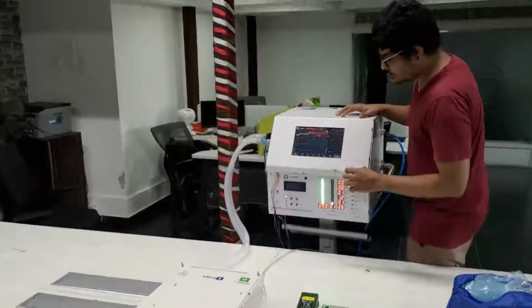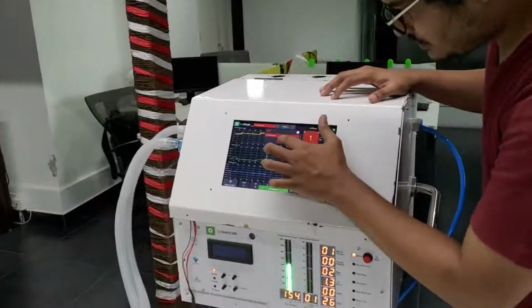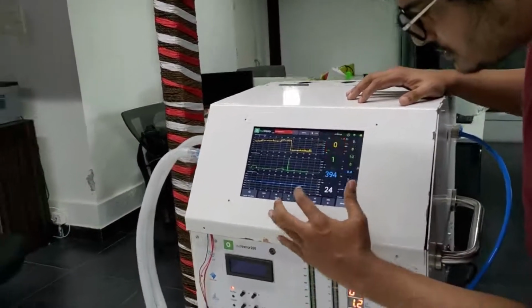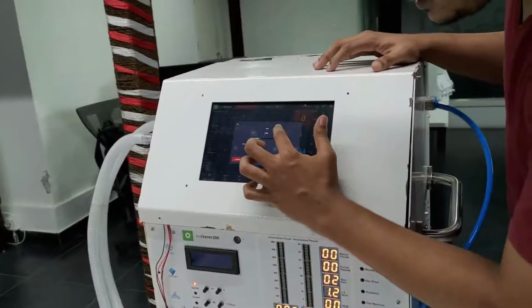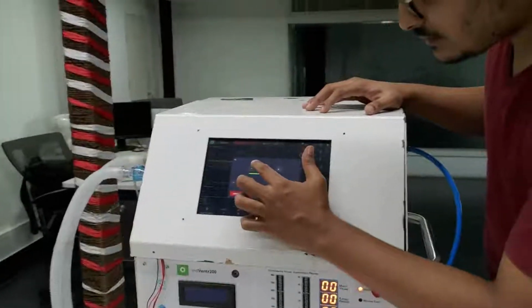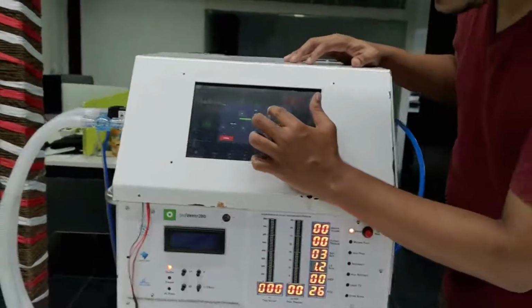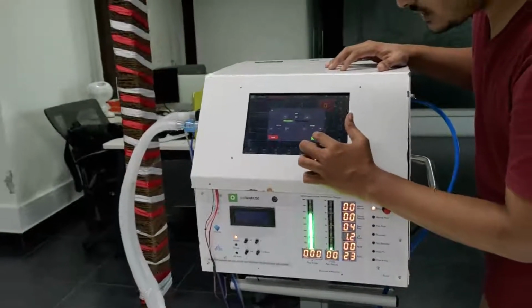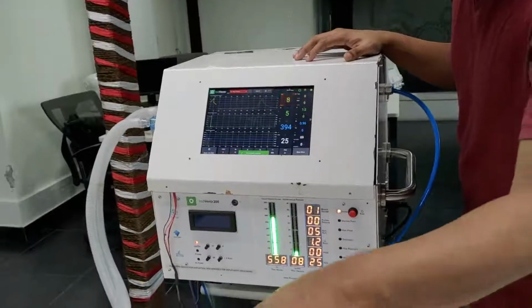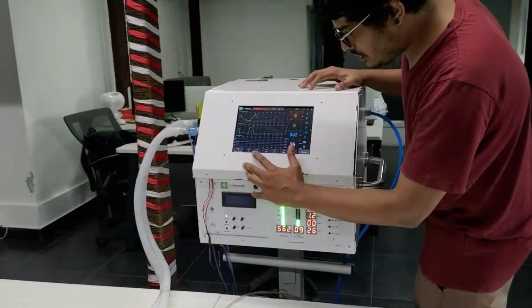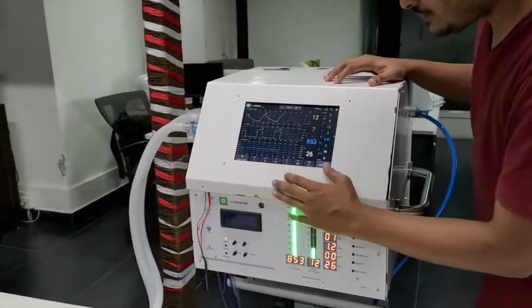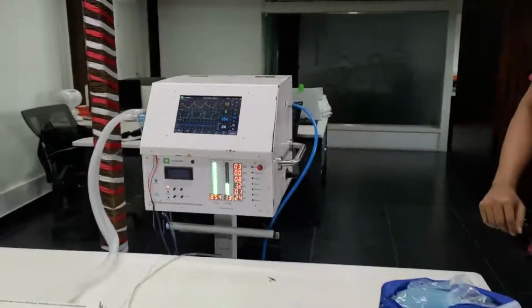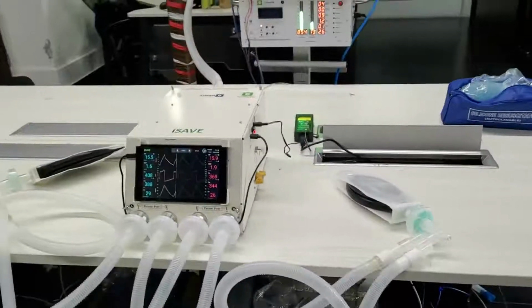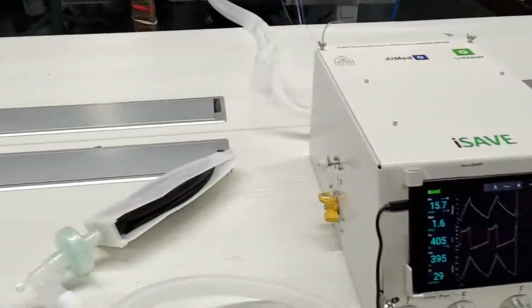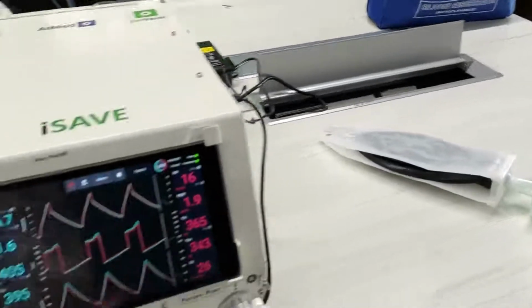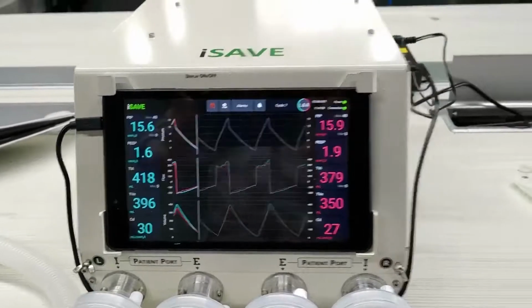I'm going to start ventilation from our ventilator. Let me set our tidal volume. I'm going to just set it to 800. You should have somewhere around 400 tidal volume for each patient. RR is set to 15, I:E is set to 1:2. Now you can see that iSAVE is already distributing the ventilation to the two patients. We're in VC-CMV mode on the ventilator. You can see that the lungs are rising and reducing.